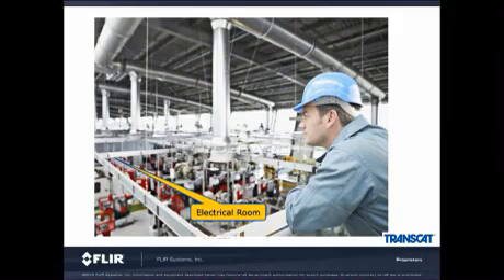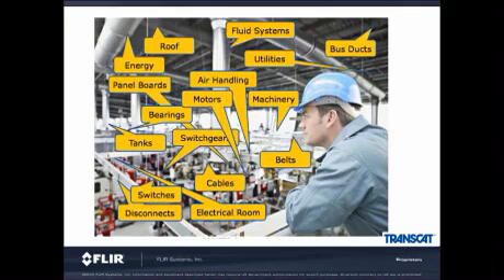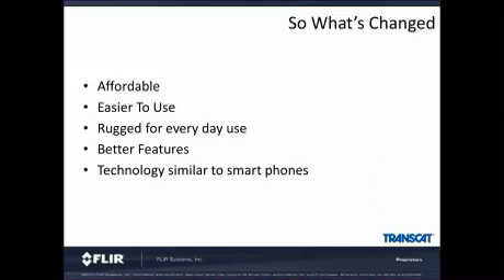Thermal cameras have generally been considered too expensive and too technical for your average maintenance technician. In fact, the major use of the thermal imager has been in the electrical room or service of your industrial plant. This is usually where your most expensive equipment is located and what can do the most damage if it failed. However, as you go to this part of the plant, you pass by all the other potential applications that you can use the thermal imager on. Since the equipment you walk by will have its own unique temperature scan, when healthy or sick, you should scan these too. And in this picture, we're showing pictures of roofing, energy, bearings, motors, bus ducts, tanks, belts. All of these are potential applications that a thermal imager can help you solve the problems that plague the plant every single day.